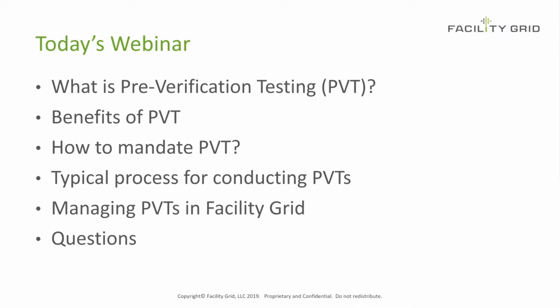How would you mandate inclusion of pre-verification testing into the project requirements? Well, first, the PVT process shall be documented in the project scope of commissioning activities, along with the extent of equipment to be pre-tested. This can be done in the general commissioning requirements specification, 019113. Also, the requirements for the pre-verification testing shall be included in the commissioning plan. Then, the pre-verification testing shall be reviewed during the commissioning kickoff meeting and also during the controls integration meeting.